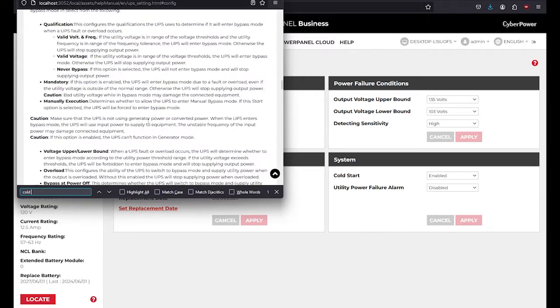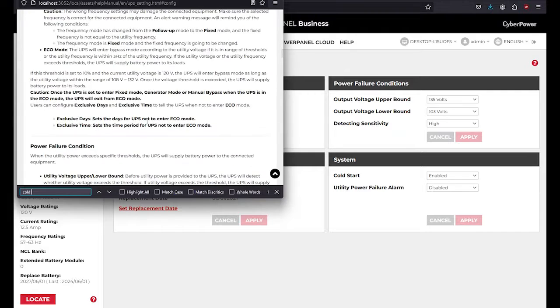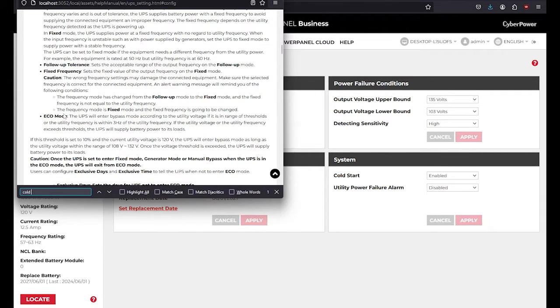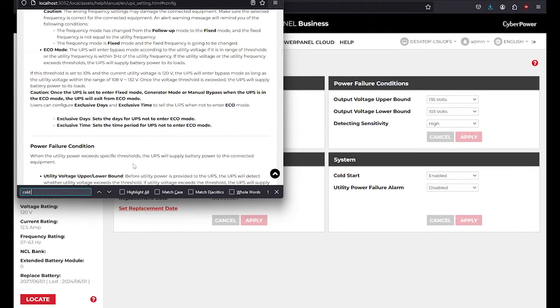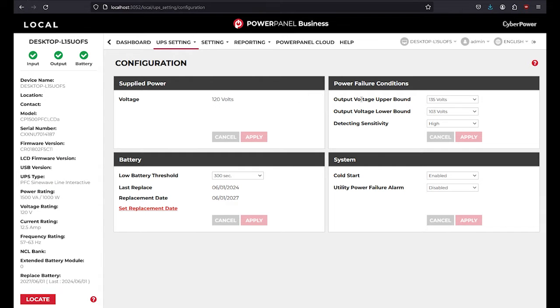And then I saw something about eco mode. Do we finally have a written description? The UPS will enter bypass mode according to the utility voltage, if it's within the range of thresholds, or the utility frequency is within 3 Hz. If the utility voltage or frequency exceeds thresholds, the UPS will supply battery power to its loads, unless it's in fixed mode, generator mode, or manual bypass. So all eco mode means is that it's not running on the inverter, it's in bypass mode - the mains power is fed directly to the load, since this isn't a double conversion UPS. Although we don't seem to have an option to disable eco mode to begin with.